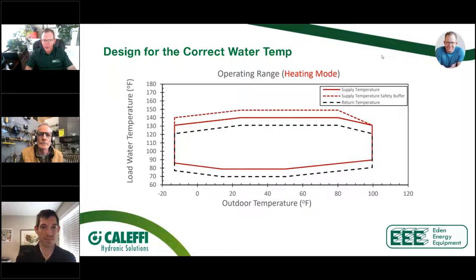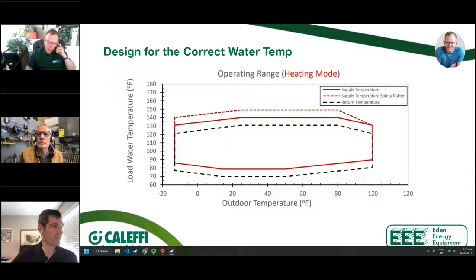So the other thing I have here is I just wanted everybody to see, because certainly there are scenarios where we're seeing manufacturers saying, hey, we've got a vapor injected unit that can produce 160 degree water. Even if it can produce 160 degree water, we're going to ask, why are you doing that? Your COP is going to be terrible. This is actually an operating table for 410A on a vapor injected air to water or water to water. Both would be in the same boat.